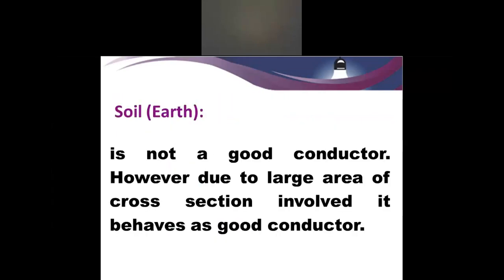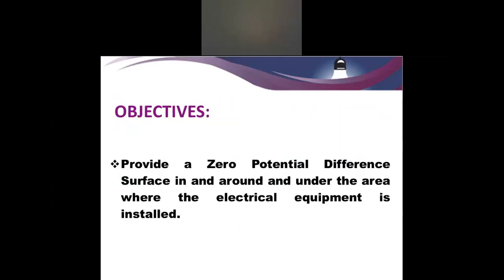Going to the next level, as I said about step potential and touch potential, our main objective is to create an earth mat, or earthing, to create a zero potential difference surface in and around and under the area where the electrical equipment is installed. I'm talking about substations typically, because once we understand substations, we can always apply it to any smaller area.